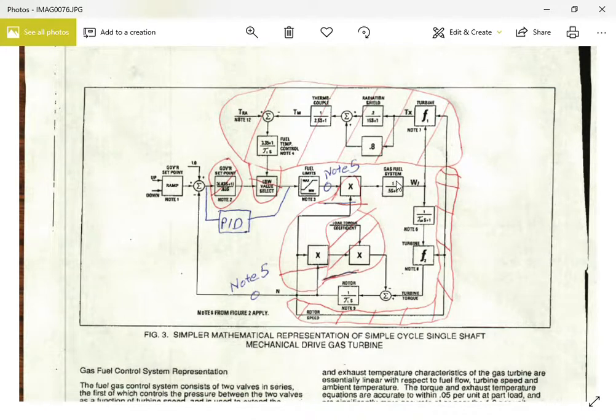So I included the gas fuel system, the delay of the turbine torque calculation. Then I summed it. This load torque was included, even if I cut it out. This is the value for rotor inertia, and what they're saying here is it's actually a slope. If you take that transfer function, you're going to multiply times tau 1, is what it means. Tau 1 is 17.